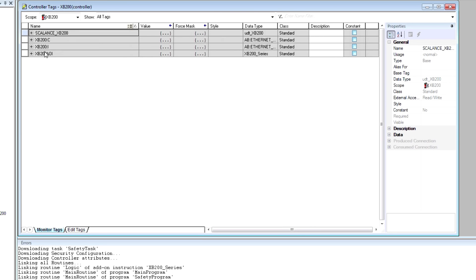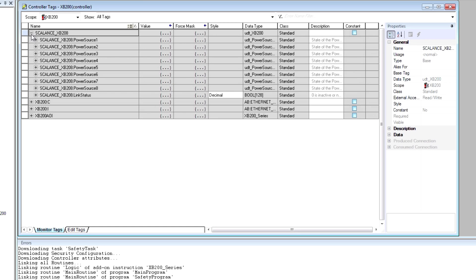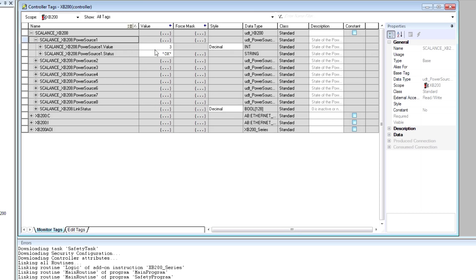If I open monitor tags and expand, I can see the AOI. The UDT for the AOI breaks out the power source. There are up to eight power sources. And if I expand PowerSource1, I can see that I am powered from PowerSource1. Status is OK.